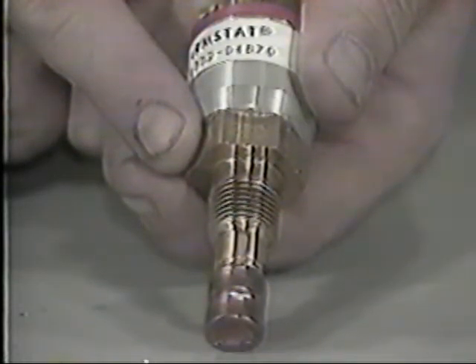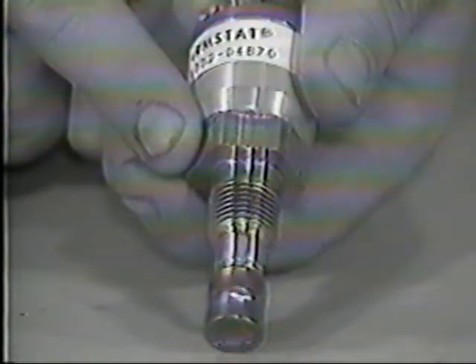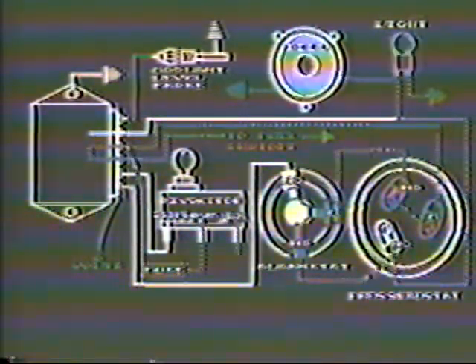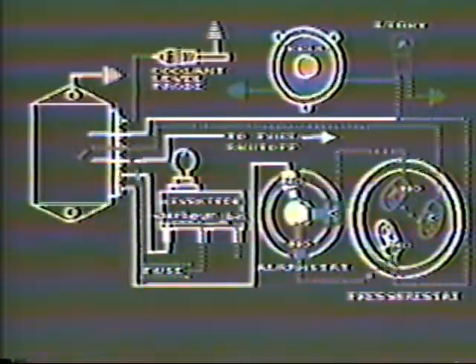The alarm stat we're using alarms at 214 degrees and shuts down at 220. As engine temperature reaches 214, the alarm stat NO switch closes, giving voltage to the light and bell and causing an overheat alarm. Again, this is identical to the 9033 and 9032 systems. If temperature continues to rise, the alarm stat NC switch will open at 220 degrees. This removes voltage from module terminal 1. As voltage vanishes from terminal 1, the module instantly opens the run switch, disconnecting voltage from the fuel shutoff and causing a shutdown.